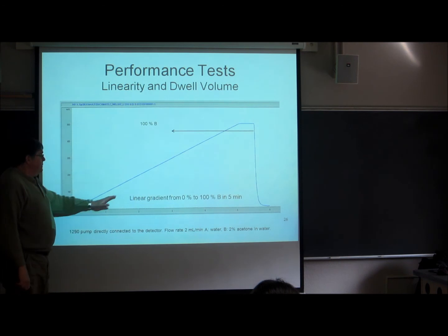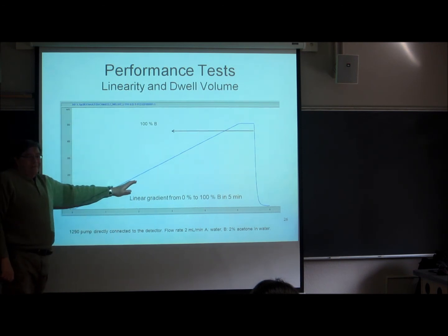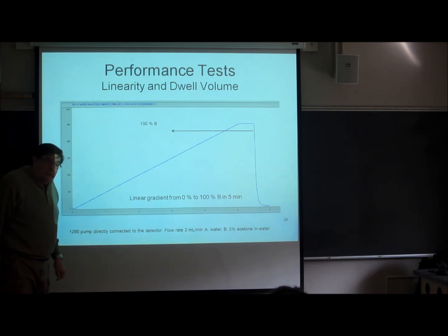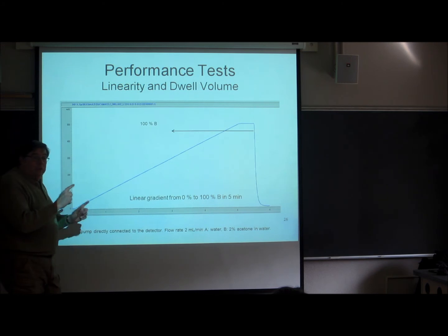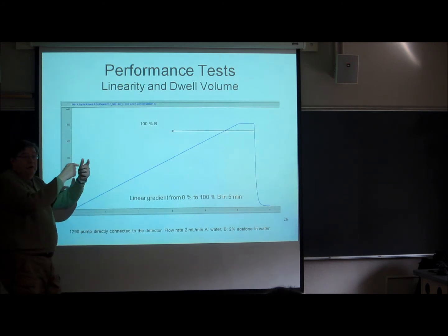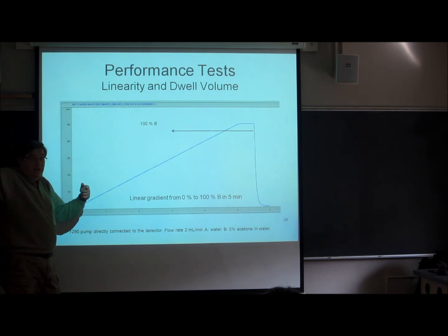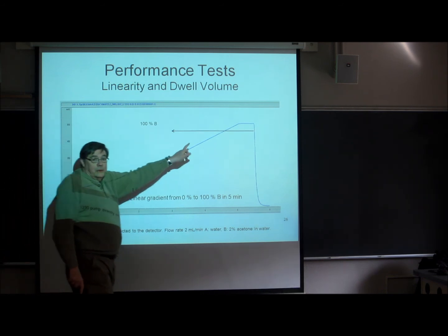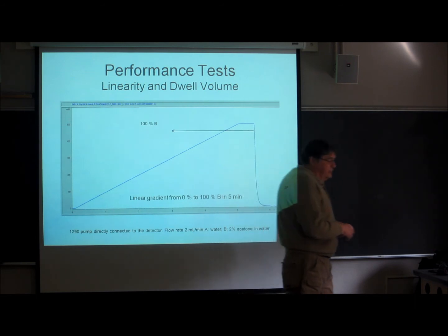Okay, this has to be right. It has to agree with the settings that you have on the instrument. If it doesn't, then one of your pumps is going too fast or too slow. So this is a routine quality check. You follow me? So you have two pumps, one of which pumps A solvent, the other B solvent. They join together, merge and mix, and then go through to the detector. And to check the speeds of those pumps, you do a sloping line like this. Very straightforward.